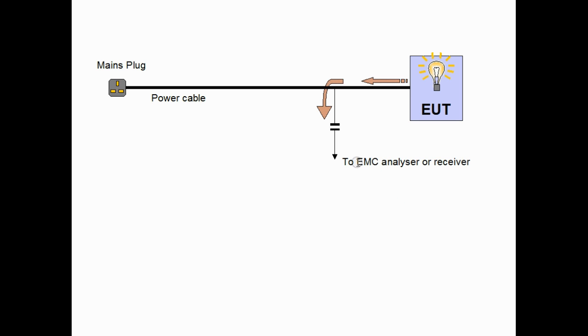The easiest way to do this is to capacitively couple to the cable so that we can extract the interfering signal and send that to our analyzer. So basically we're measuring voltage. This is simple enough to do.